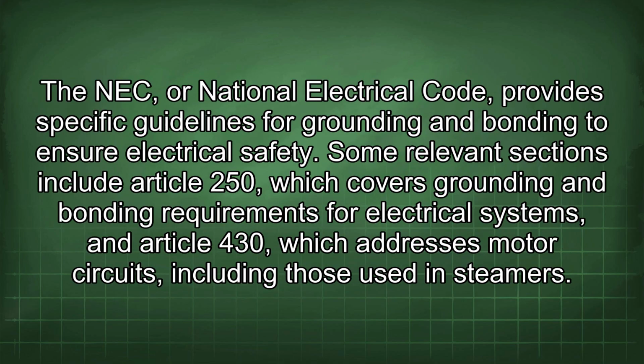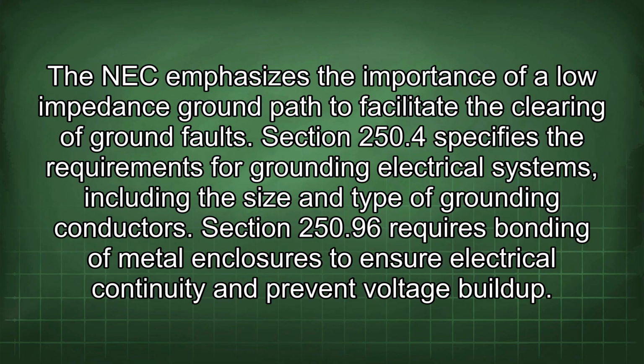The NEC, or National Electrical Code, provides specific guidelines for grounding and bonding to ensure electrical safety. Some relevant sections include Article 250, which covers grounding and bonding requirements for electrical systems, and Article 430, which addresses motor circuits, including those used in steamers. The NEC emphasizes the importance of a low-impedance ground path to facilitate the clearing of ground faults. Section 250.4 specifies the requirements for grounding electrical systems, including the size and type of grounding conductors. Section 250.96 requires bonding of metal enclosures to ensure electrical continuity and prevent voltage buildup.